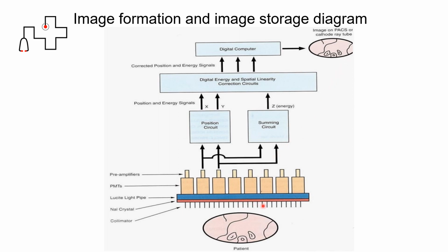The collimator is located at the face of the detector. So where the photons from radioactive sources first enter the camera. The collimator is used to separate gamma rays and keep scattered rays from entering the scintillation crystal. Resolution and sensitivity are terms used to describe the physical characteristics of collimators.